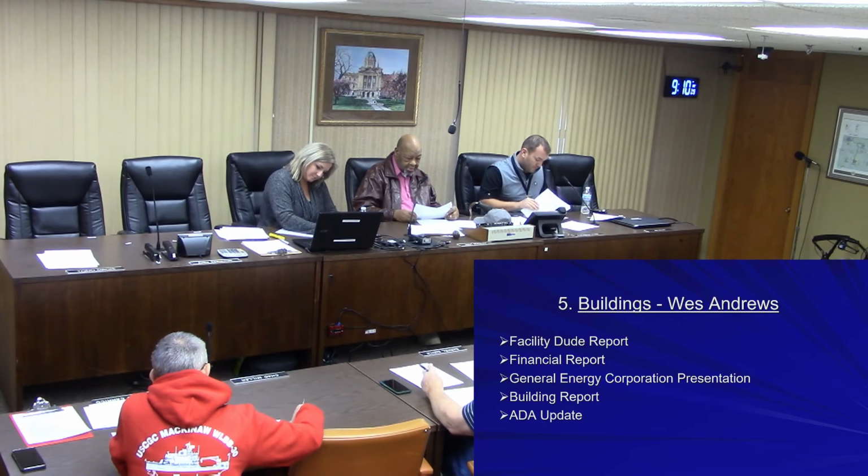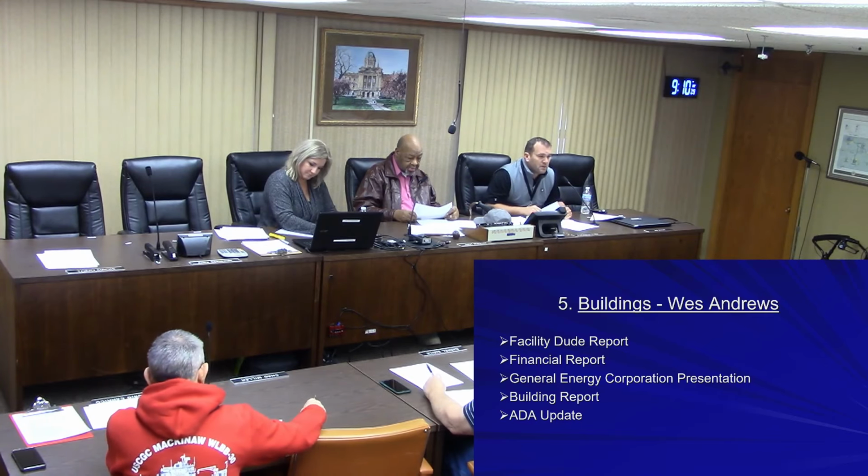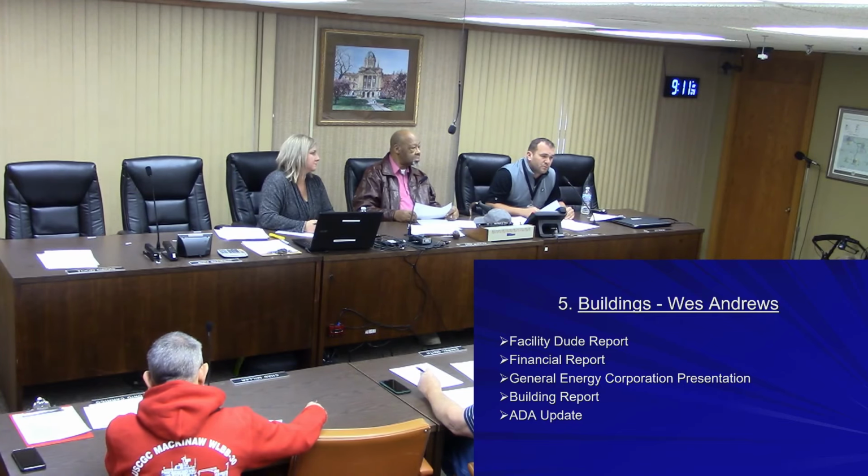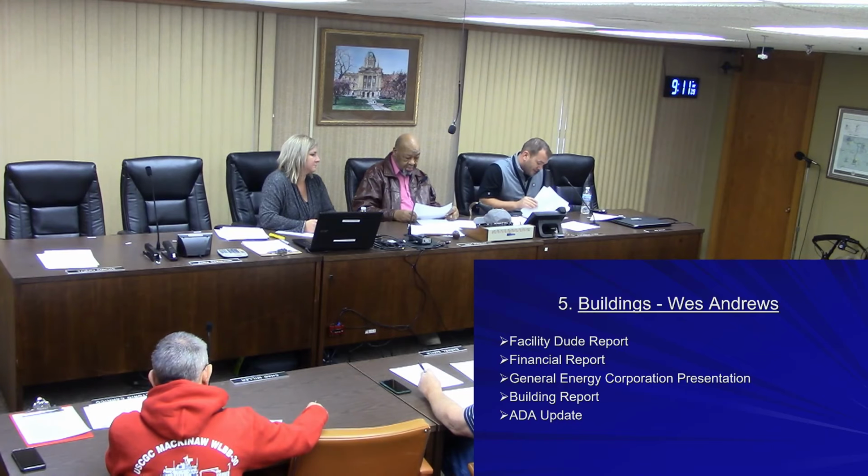Another considerable expense, we spent about $1,200 on batteries. We've talked a lot at this committee over the years about preventative maintenance and what we do and what we don't do. Well, there's an example. I believe all the batteries were over 5 years old in our generators. So we went through and we replaced all the batteries in our generators at the various buildings. And we did that in-house, so the only expense we had was for the actual material. So of the 17,000, I've outlined about $5,000 worth of expenses. So if there's any other questions on this, I can try to figure it out.